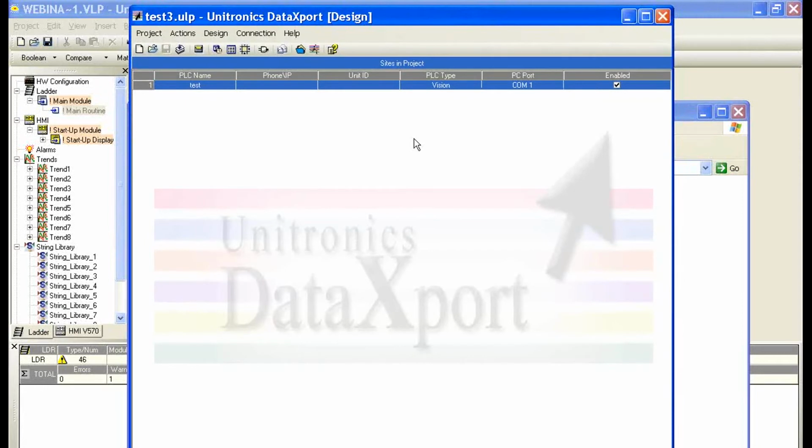I want to create another scheme. So this is nice for time-based events, or if you manually want to come and connect. Again, with a time-based event, we need to know exactly how long we can let the PLC record data before the data table fills up. Since this is the way, in this case, that we are creating more space or moving the information from the data table, it's very important that we get to the data table and clear it out before we fill it up.